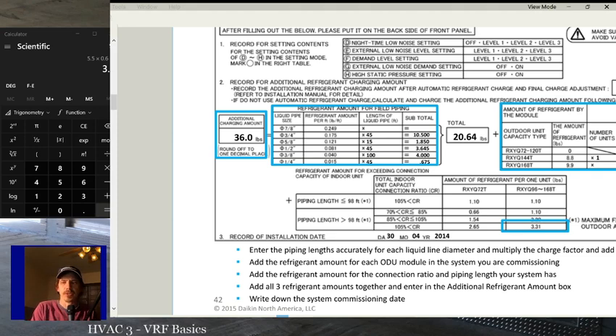And when it comes to residential or split systems in particular, also make sure that the size of your evaporator doesn't change how much refrigerant you're supposed to have. I know looking those up so you can charge by weight can be a hassle when you've got all those factors to consider when you're weighing your charge in, but I'm telling you, if you know how many pounds are supposed to be in there, you're good to go, man. And when it comes to systems with microchannel coils or VRF systems or mini splits, you need to do it anyway. So it's better to be in a habit of doing something that can be done every time than something that can only be used some of the time.